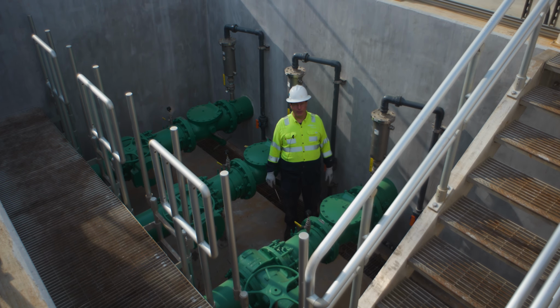The main purpose of the check valve is that it closes after the pump is done pumping so that the force main pressure doesn't come back and dump into the wet well. And also, if there are multiple pumps running and one should be at a higher pressure than the other for whatever reason, the check valve will close and not allow it to pump back through the other pump. All these pumps pump around the same, so they'll just both open together and they'll pump even more when two pumps are running. These pressure gauges are used so that we can look at the pressure while the pumps are running. And the plug valves are used so that you can isolate each pump for maintenance or for working on the check valve, the pressure or the air release valve, or changing out the pressure gauge. In this case, they have individual valves on them, so hopefully you wouldn't have to replace the saddle.